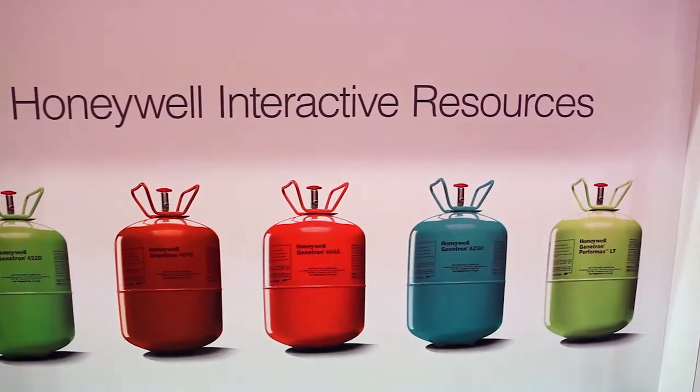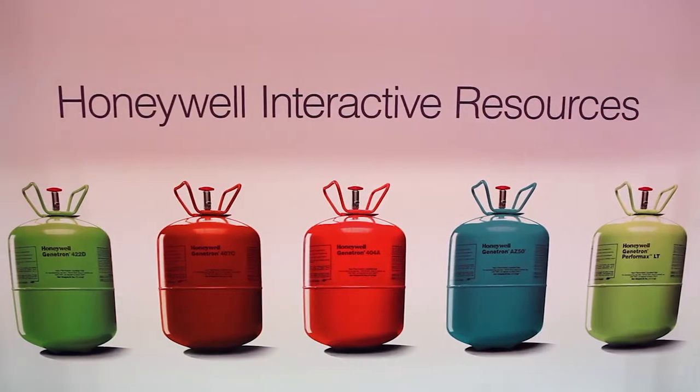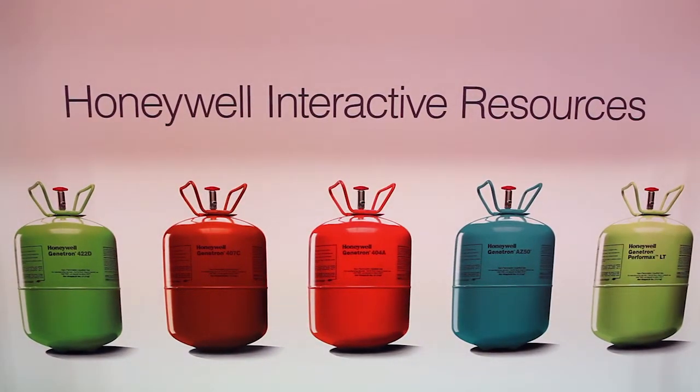And for our contractor viewers here, what are they looking for when they're replacing R22? Well, on the air conditioning side, what you want to look for is a product that you have reliability and easy to use. And with our product 422D, the nice thing about that is they don't have to go through oil changes. It's basically evacuate the system, clean it out, you can recharge it with 422D. The pressures and temperatures are going to be very similar, so it's an easy transition for them and something with a lot of history and reliability behind it. So it makes their job pretty simple.